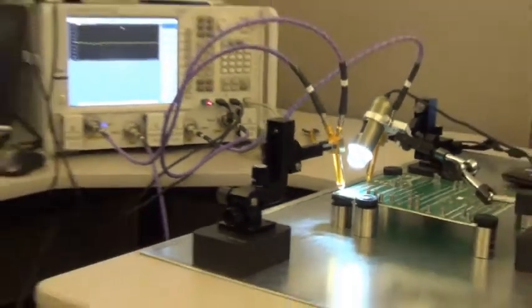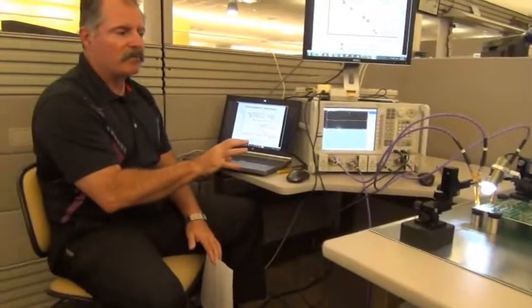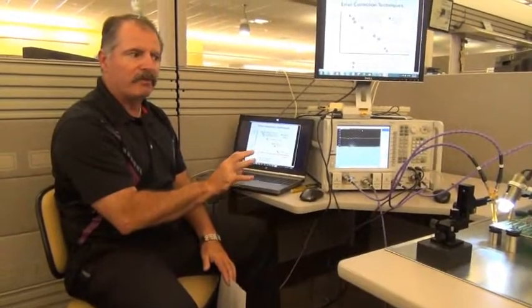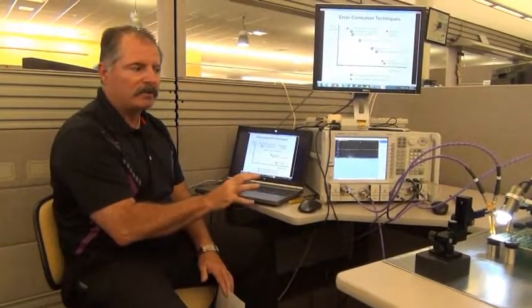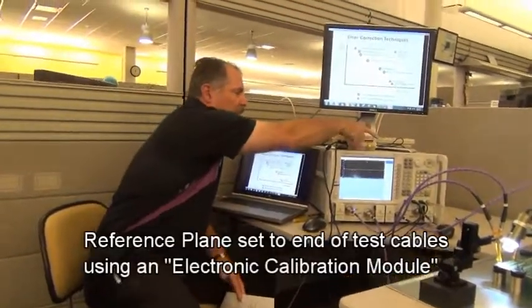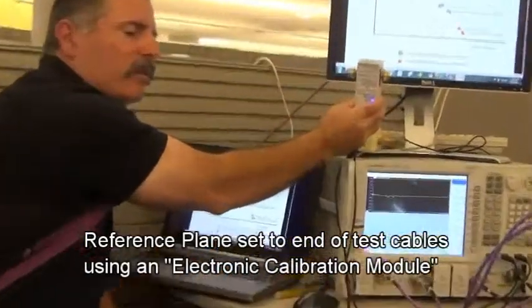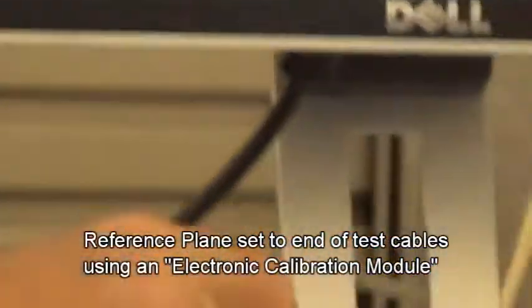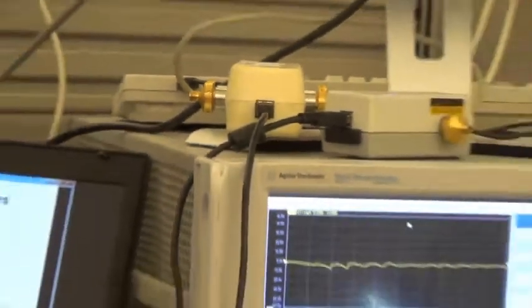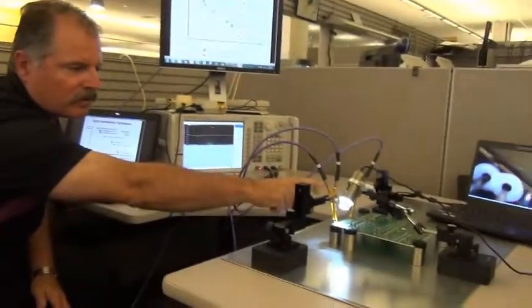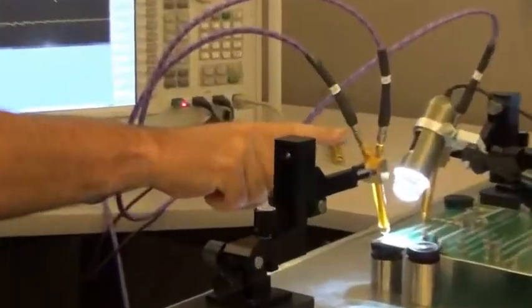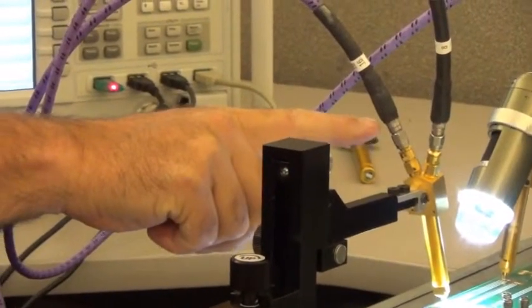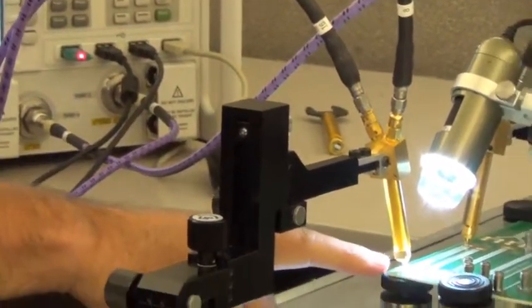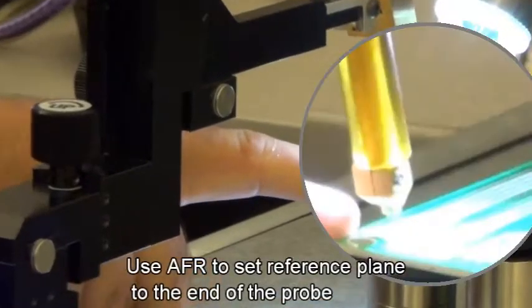calibration. To be more specific, with this system we've first done an SOLT with an ecal, a short open load through to the end of the test cables. So we've got a coaxial environment with SOLT. But what we really want is the reference plane down here at the end of the probe tip.